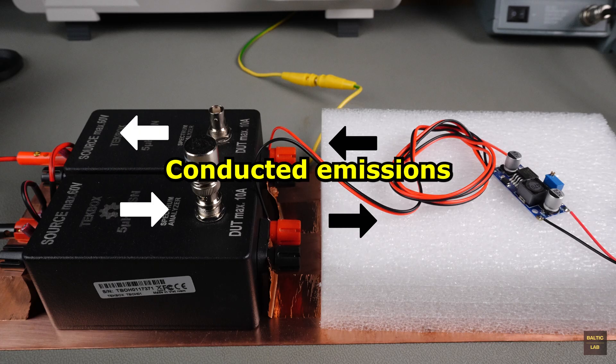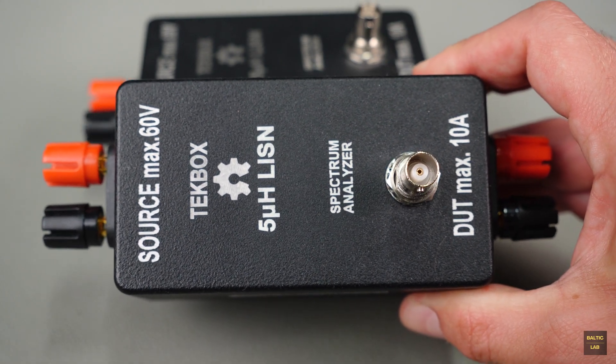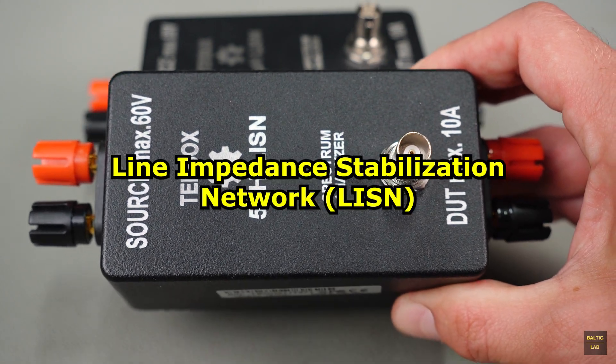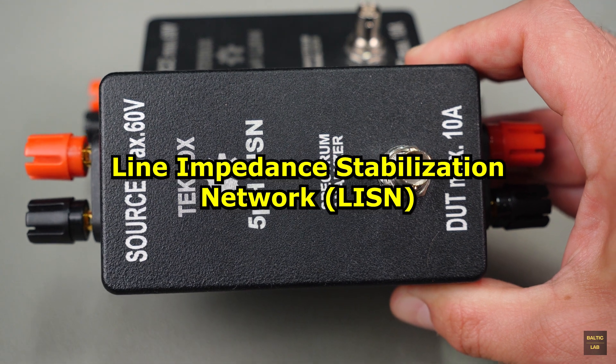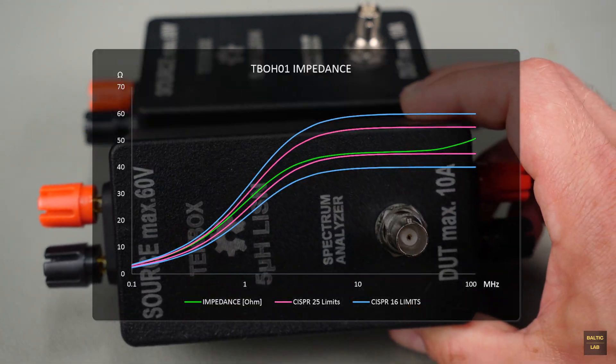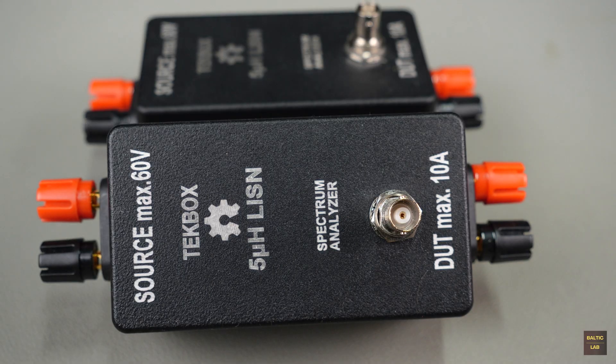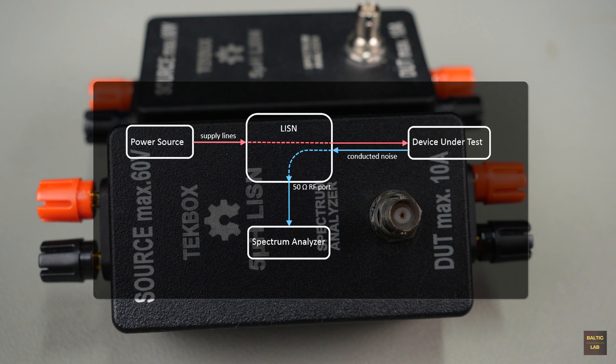To measure conducted emissions, we use a so-called LISN, a Line Impedance Stabilization Network. A LISN serves two main purposes. First, it provides a standardized impedance to the device under test. Second, it allows the extraction of interference signals so they can be analyzed using a measurement receiver or, in this case, a spectrum analyzer.